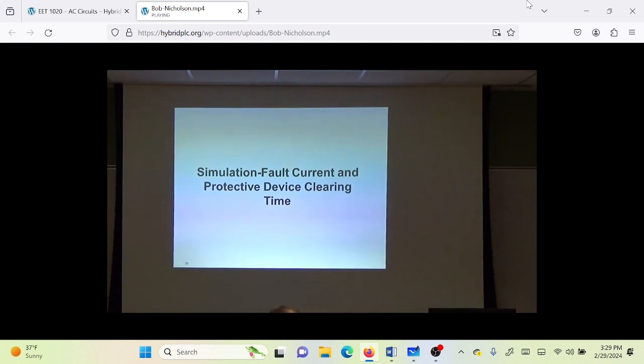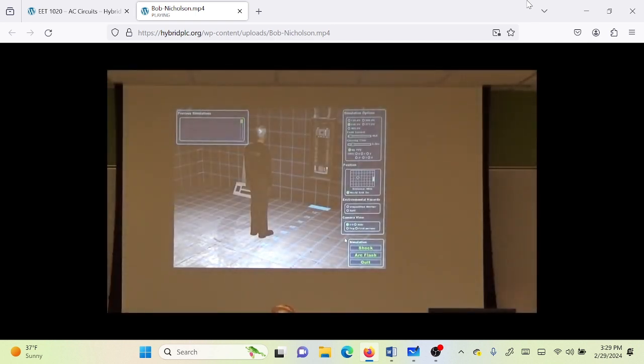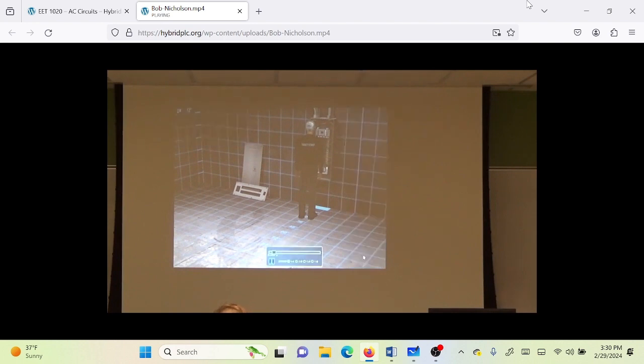Now, this is an interesting software that I'm going to make some points with to you. Whereas before I showed you a video, now I can control everything with this software. Here's voltage. I'm going to put it at 480 volts. It doesn't matter. Here's fault current. You now know what that is. That's the transformer. I'm going to put it way down to 3,000 amps. The clearing time of the upstream device is going to operate in 0.01 seconds. I'm going to move you in front of the panel. I'm going to put you about 18 inches away from the panel. And I'm going to create an arc flash.